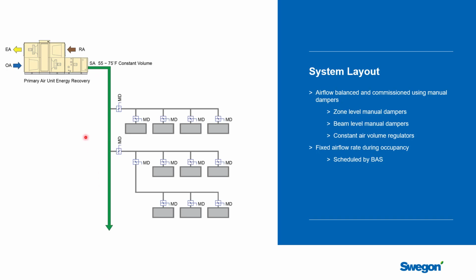And that allows you to use manual balancing dampers in the ductwork to make sure that the air is the right amount to each one of the beams. If these beams are all identical, you would use these manual balancing dampers to adjust the airflow rate to the beam that's closest to the air handling unit, but also make sure that you could deliver the right amount of air to the beam down here that's furthest from the air handling unit.